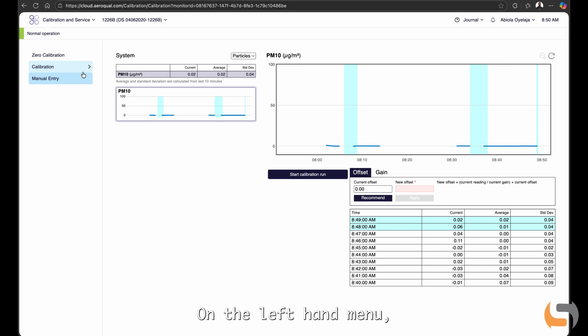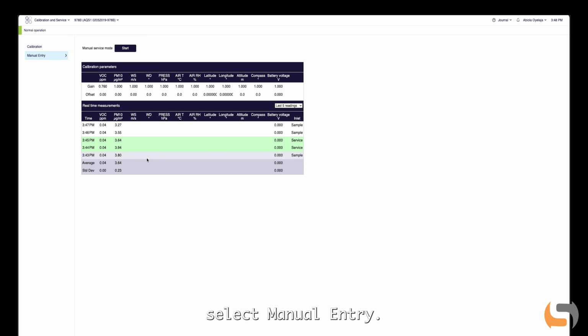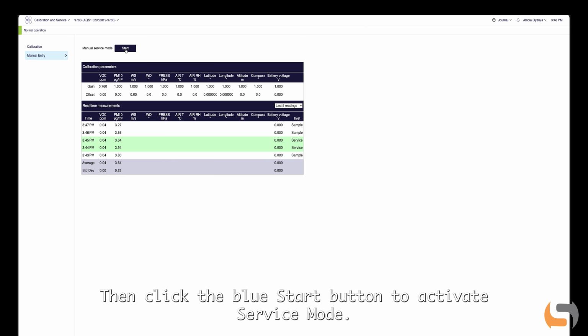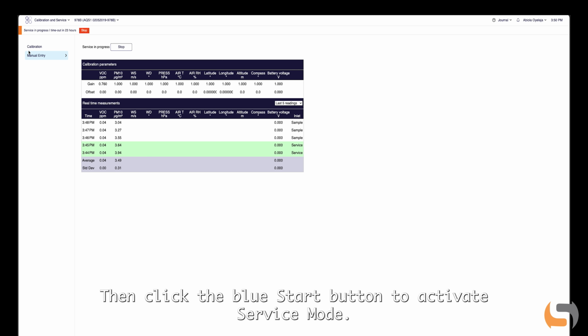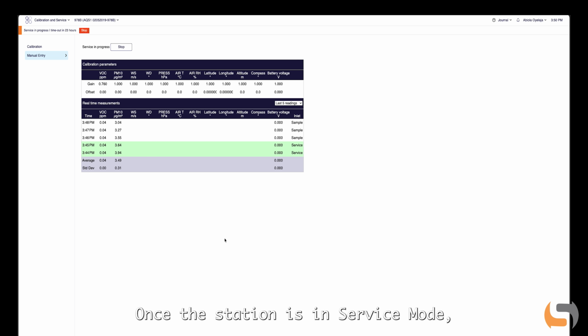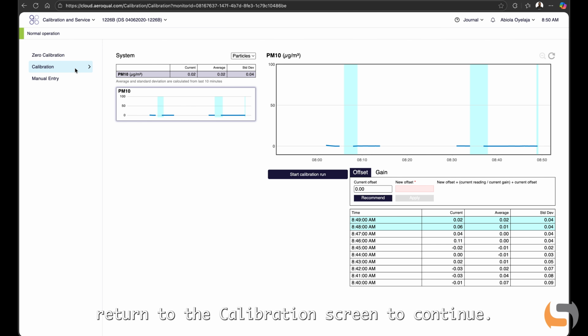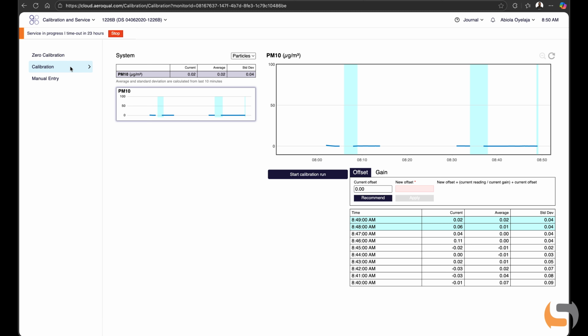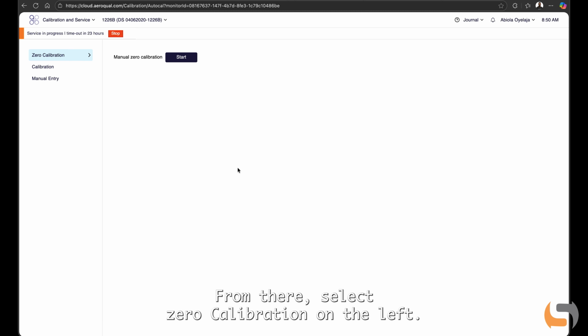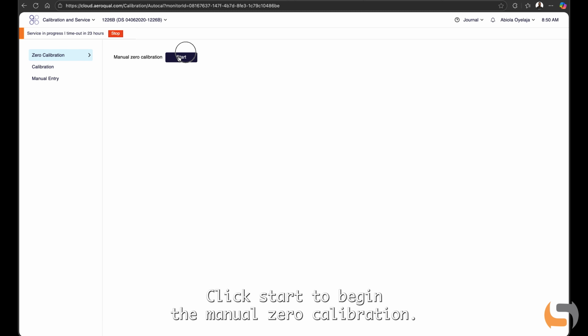On the left-hand menu, select Manual Entry. Then click the blue Start button to activate service mode. Once the station is in service mode, return to the calibration screen to continue. From there, select Zero Calibration on the left. Click Start to begin the manual zero calibration.